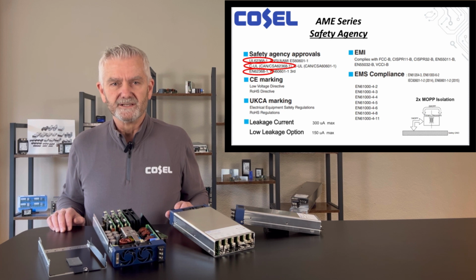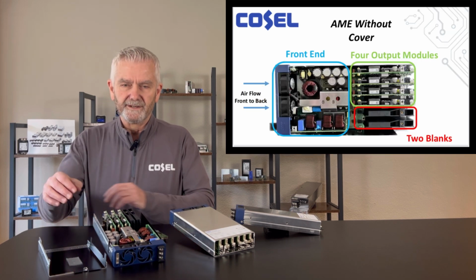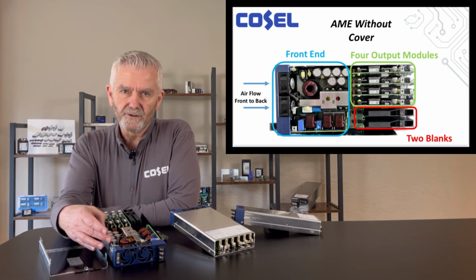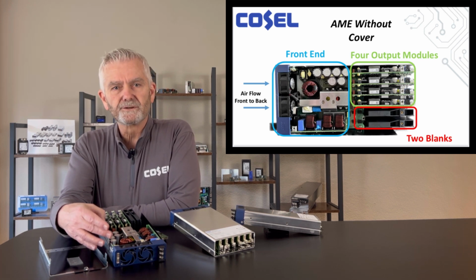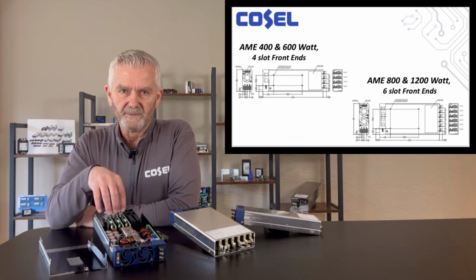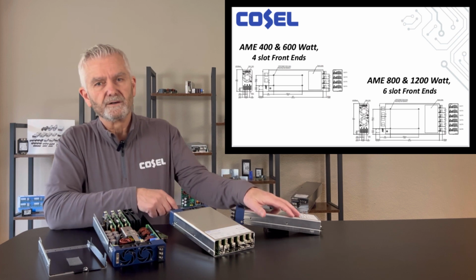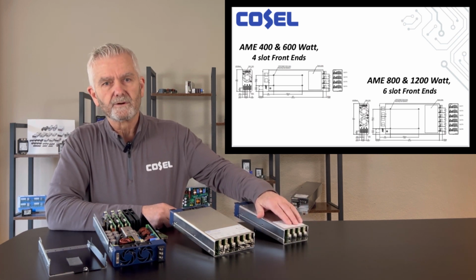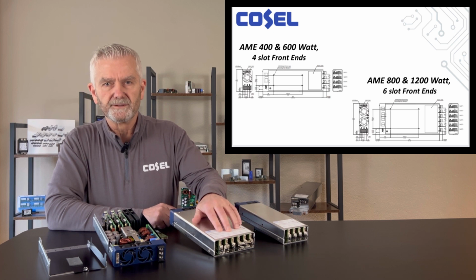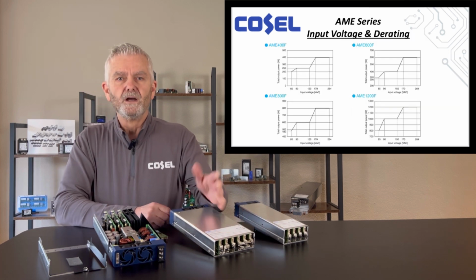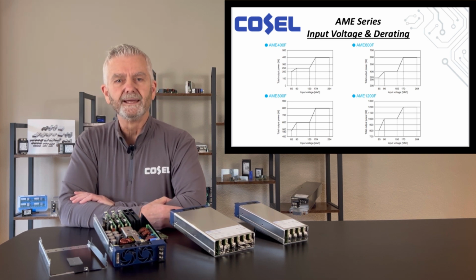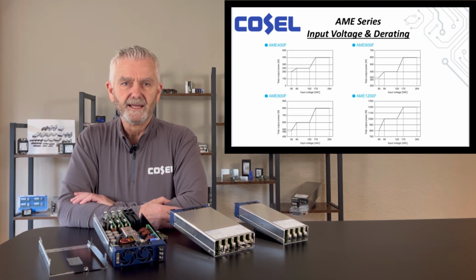Additionally, the AME series meets the rigorous requirements for ITE applications with UL 62368-1 certification. The front end houses EMC filtering, inrush current limiting, and power factor correction, ensuring stable and efficient power delivery to the output modules. The 400 and 600 watt front ends have 4 slots that accept 4 output modules, while the 800 and 1200 watt front ends have 6 slots. All 4 front ends operate over the standard 85 to 264 volt input range, and all 4 front ends begin to derate at 170 volts input as noted in the charts.